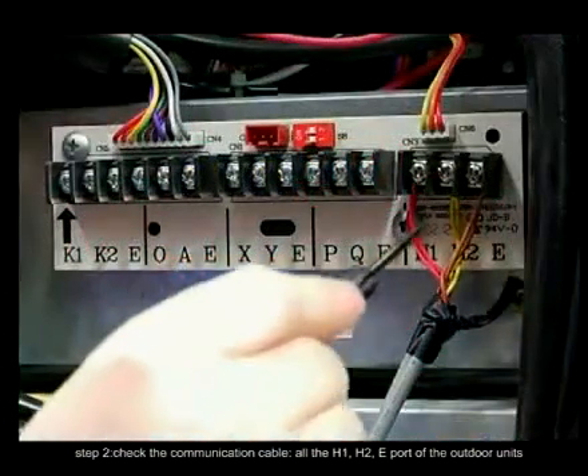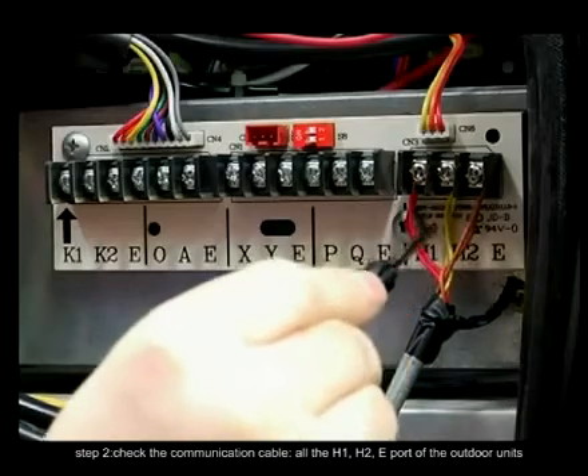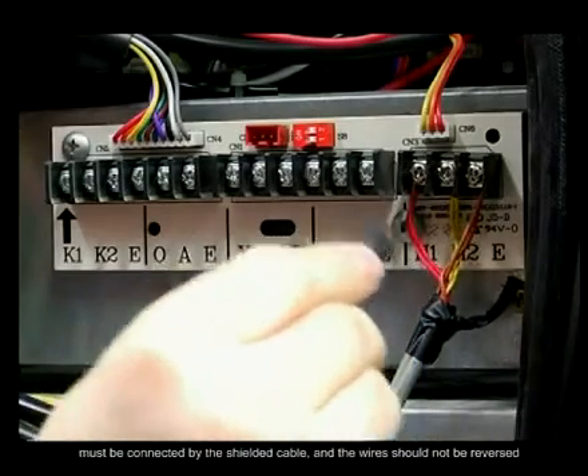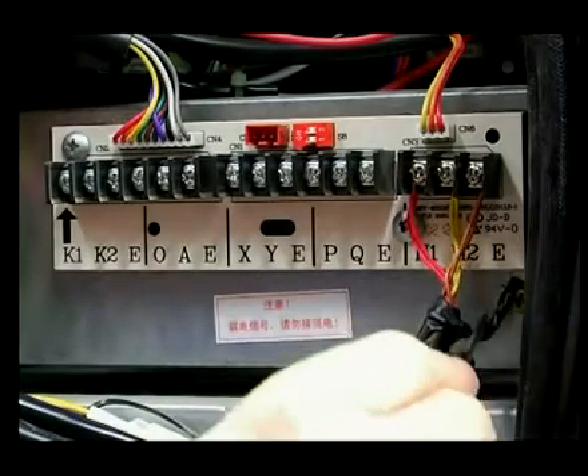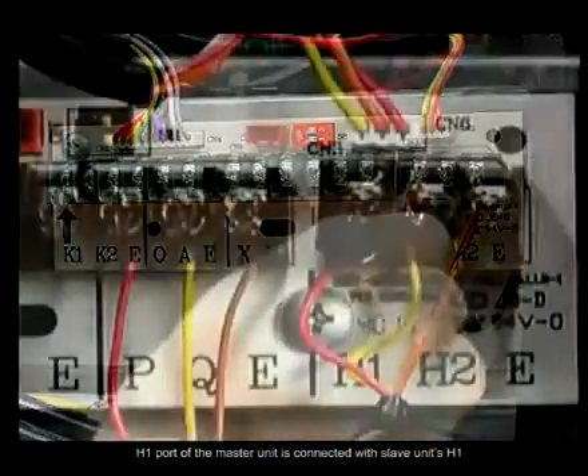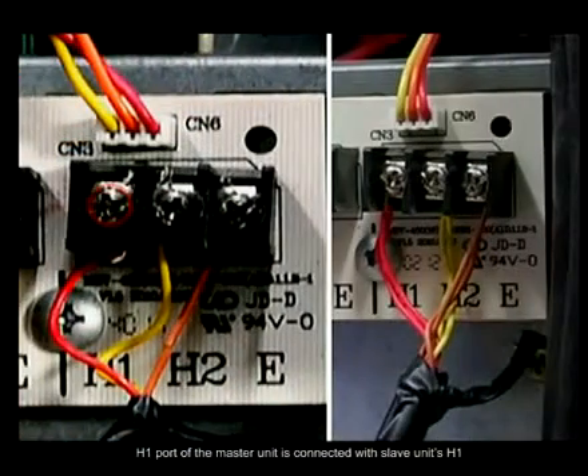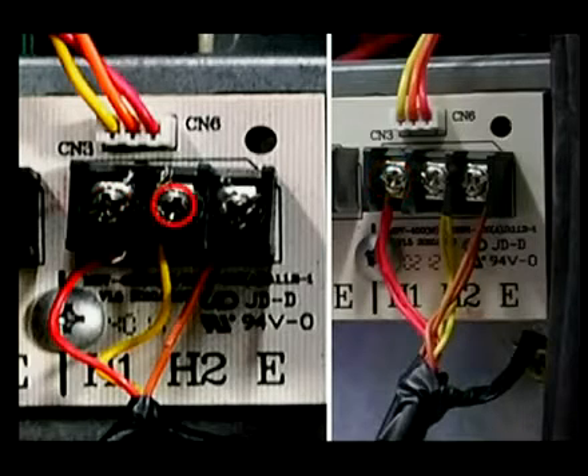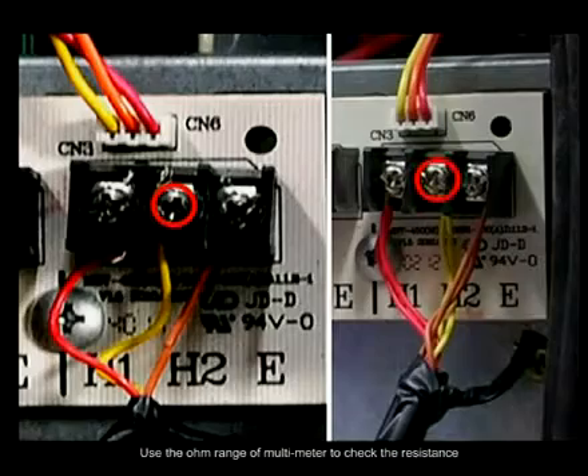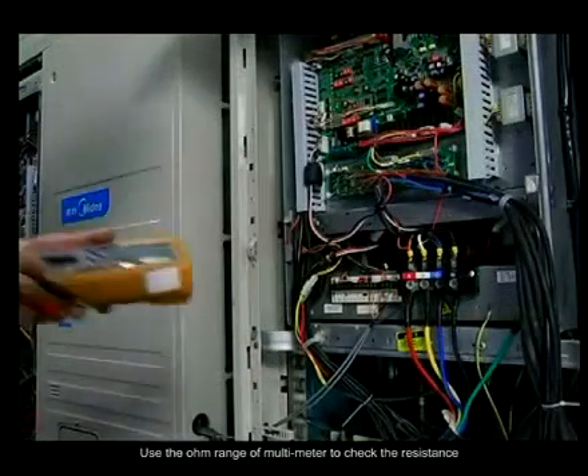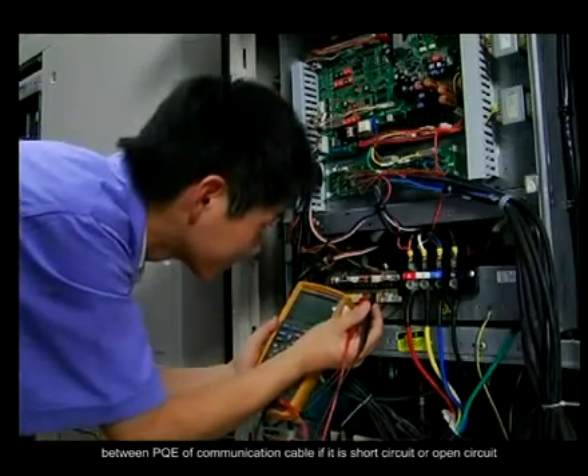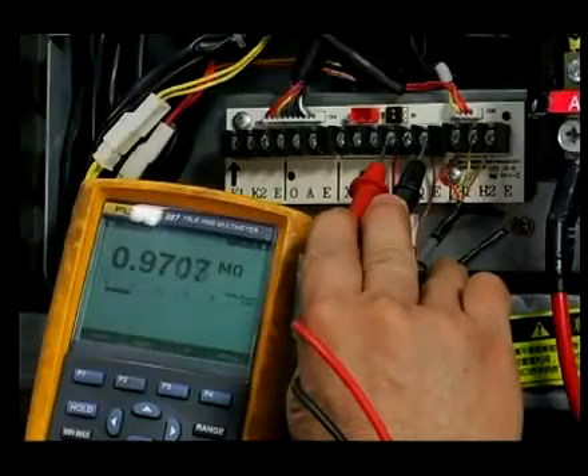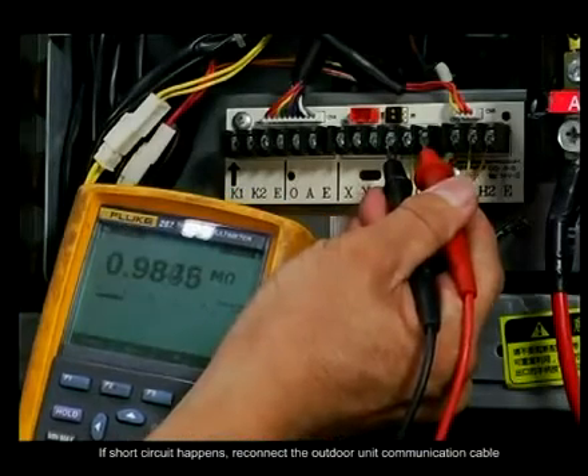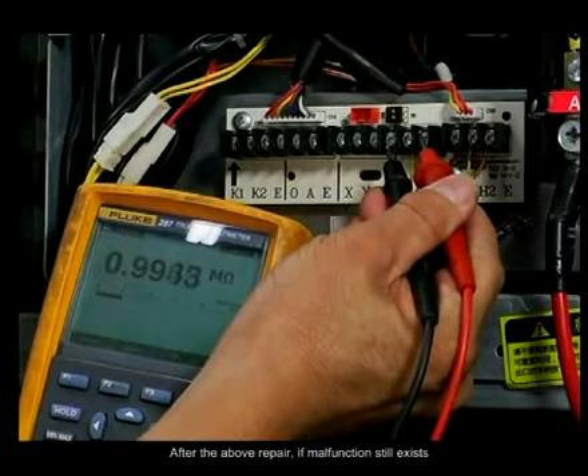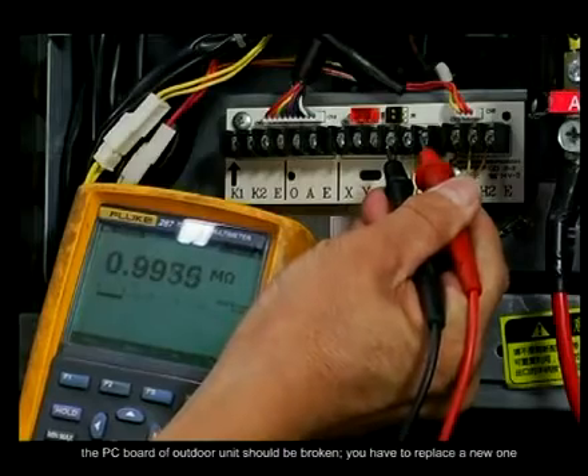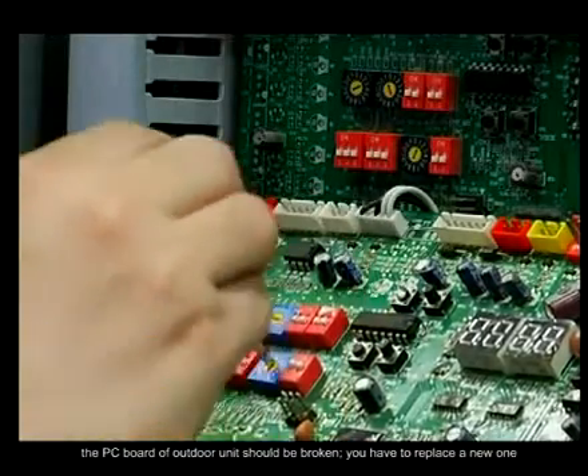Step 2. Check the communication cable. All the H1, H2, E port of the outdoor units must be connected by the shielded cable, and the wires should not be reversed. H1 port of the master unit is connected with slave unit's H1 and H2 port is connected with H2 port. Use the OHM range of multimeter to check the resistance between PQE of communication cable if it is in short circuit or open circuit. If short circuit happens, reconnect the outdoor unit communication cable. After the above repair, if malfunction still exists, the PC board of outdoor unit should be broken. You have to replace a new one.